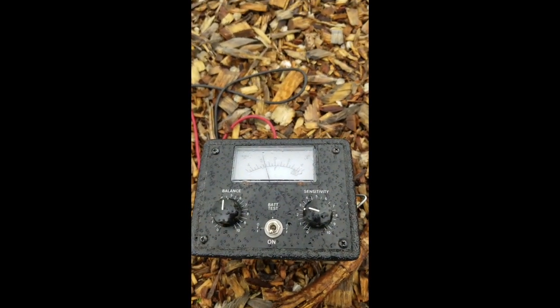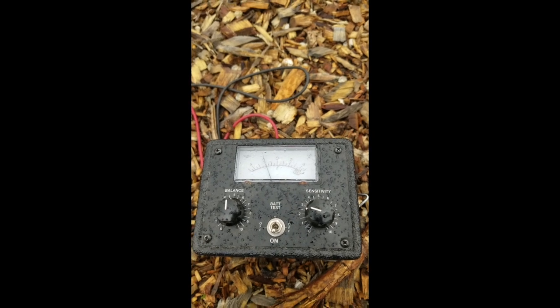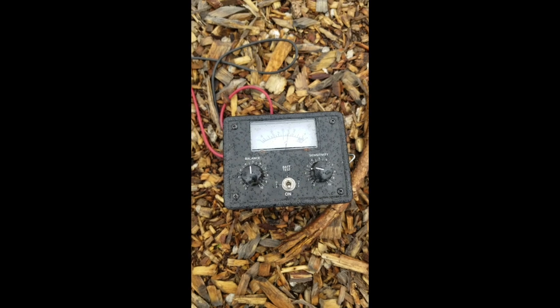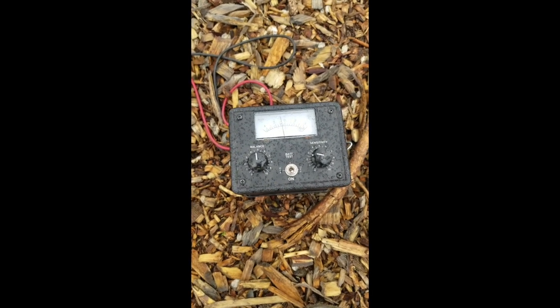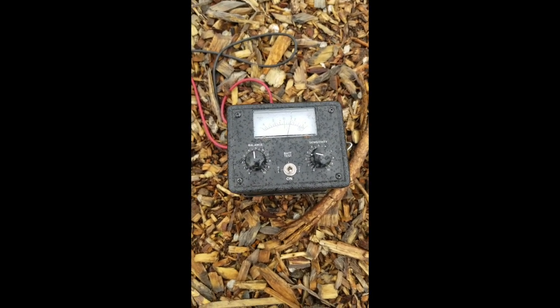It's telling me the red probe is closer. Okay. So now I'm going to pull this black probe, bring it into about a foot from the other one, and see if I still get that red deflection. It is proceeding to the red. So now I'm just going to do what we call a 90-degree walk around, and that confirms that I am on the cable route and that I have pinpointed this fault.